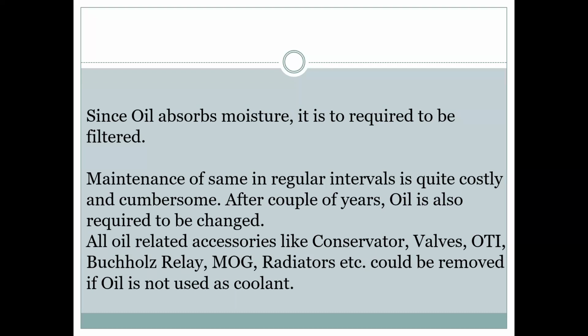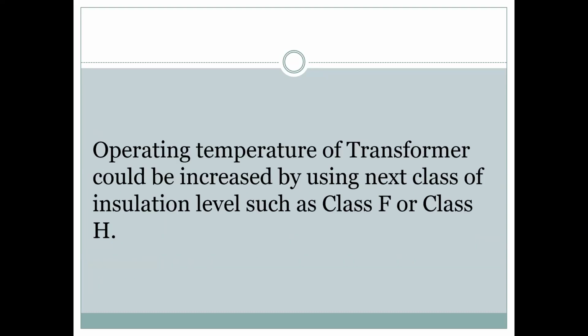There is no dripping, nothing. We have to make it clean and dry. Next. So these are all related. Now if we can increase the insulation level of a transformer class A or next generation, next level of insulation, then all these oil related things are not there. So we now come to the dry type transformer.